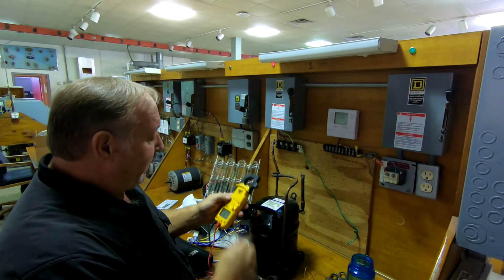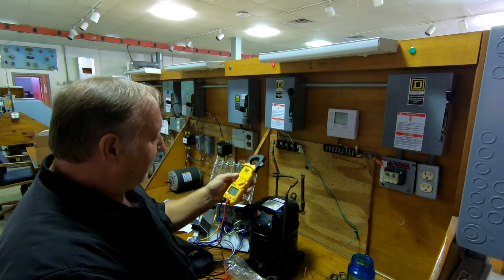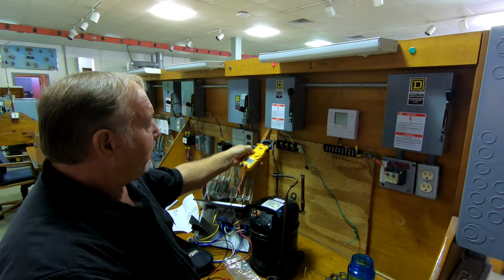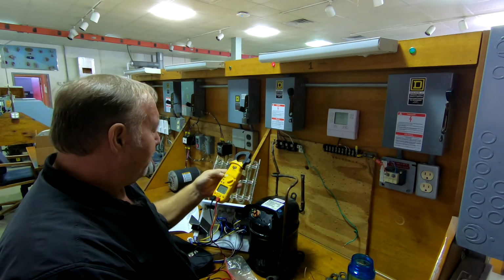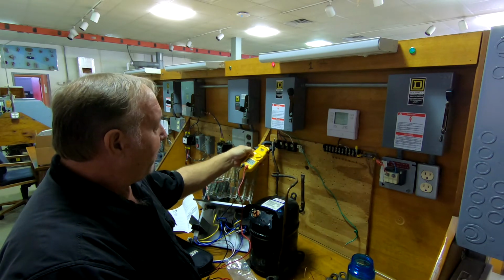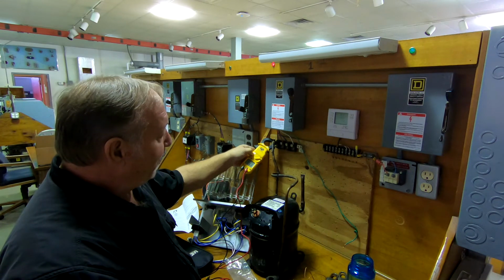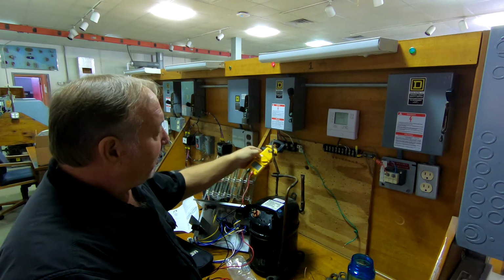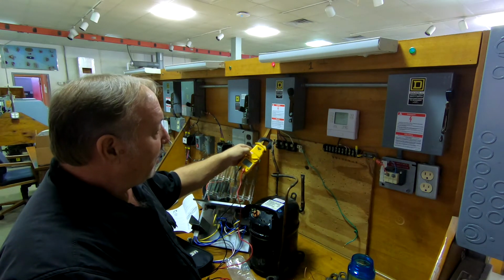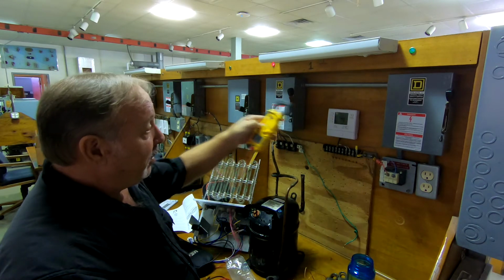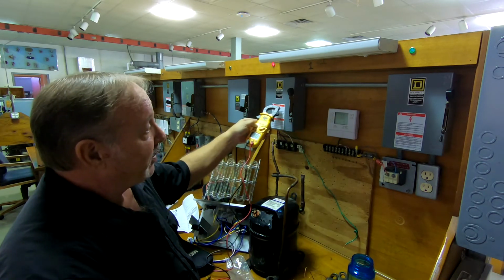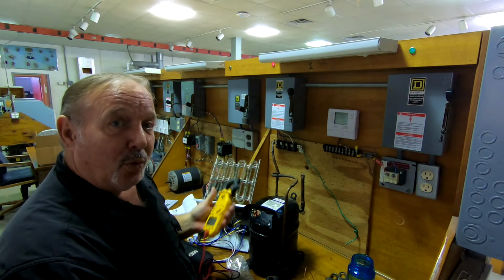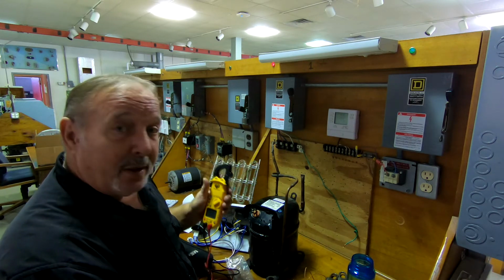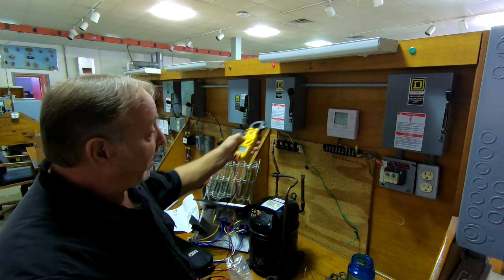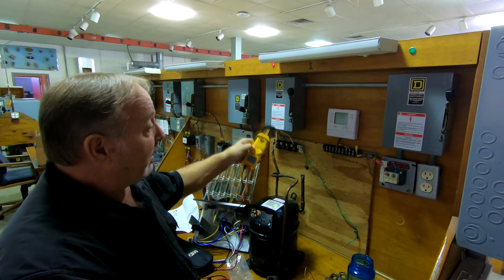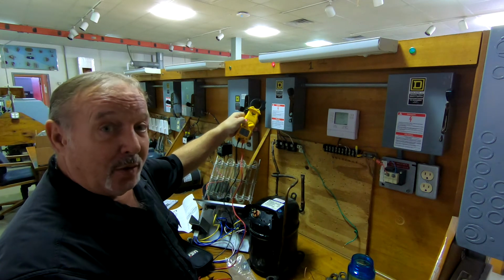Now one of the other functions that this meter has, if you set it on the voltage scale and you want to just see if you have voltage, you can press the button here that says NCV, and now you can see that just being in proximity, I'm able to tell that I have live voltage present. So that's a plus for you guys out in the field. If you come up to a piece of equipment you've never worked on and you suspect that there may be a broken wire that's possibly grounded out, this is one way to test to make sure that the actual metallic case around the unit is not live.